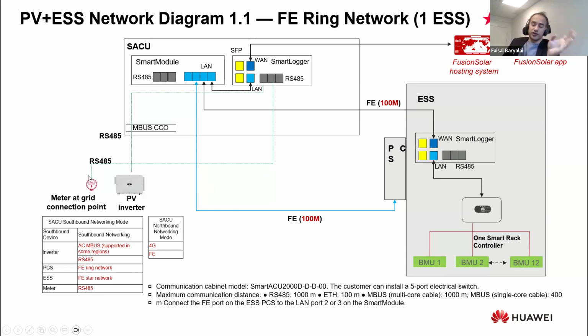We can connect furthermore, if we have smart meters or PV inverters, exactly as we do in ordinary installations. The inverter can communicate with a Modbus RTU communications line to the smart logger COM ports, or, if this PV inverter has the option to communicate through the power line M-bus, we could also communicate to the smart logger through M-bus communication. So it's very flexible how other units are connected: either by Modbus RTU, for instance, for the meter, RS485. If it's an inverter, it could use RS485 or M-bus communication if it has the alternative for M-bus.